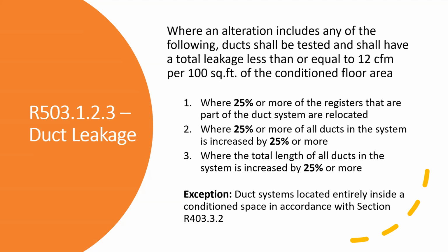So the new code says if it's entirely in conditioned space, you still have to duct test it. However, if you're part of an addition or a remodel, it's saying if you're in conditioned space, you don't.